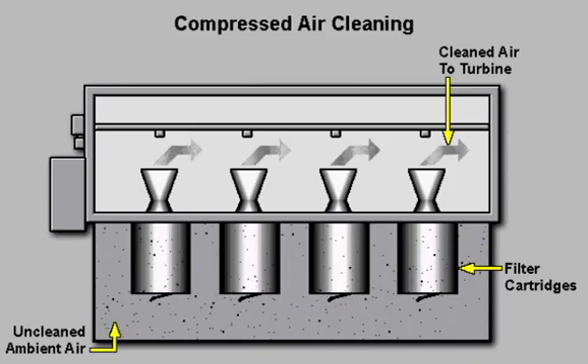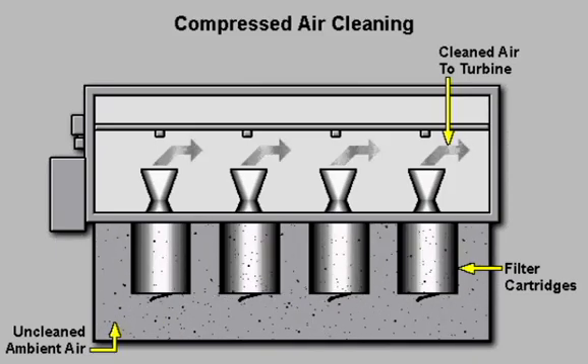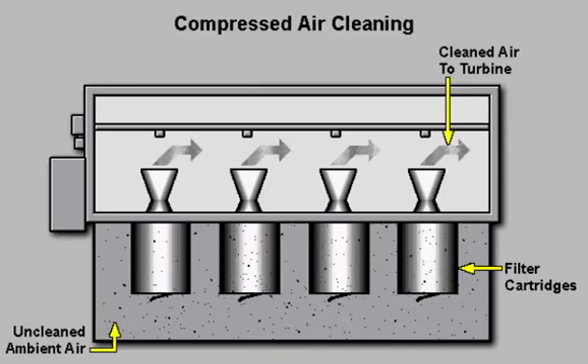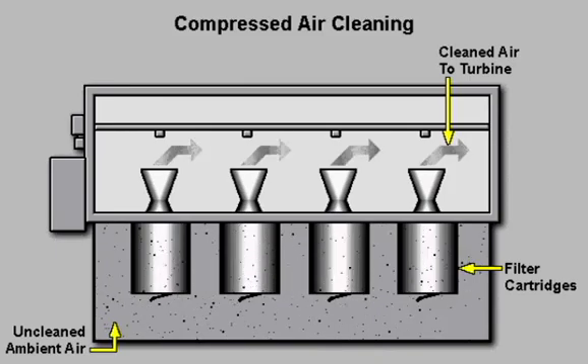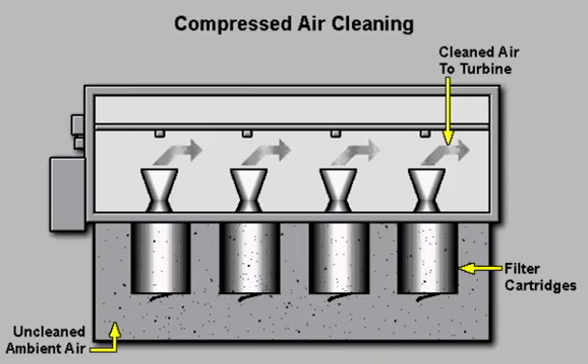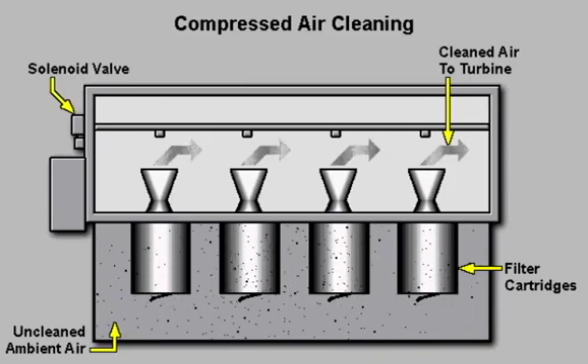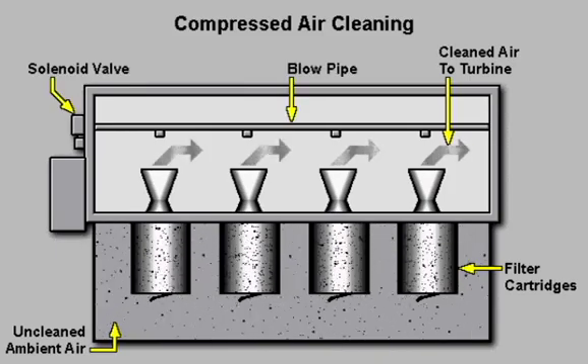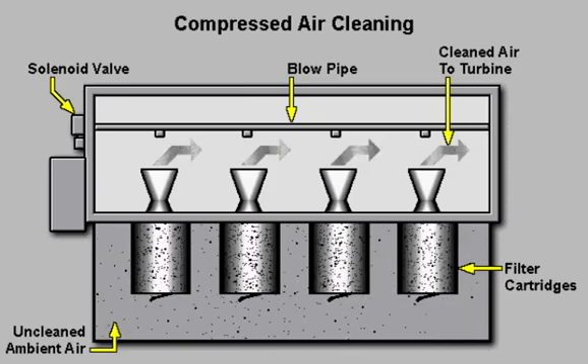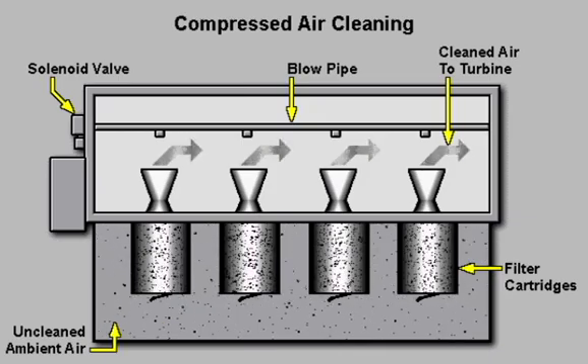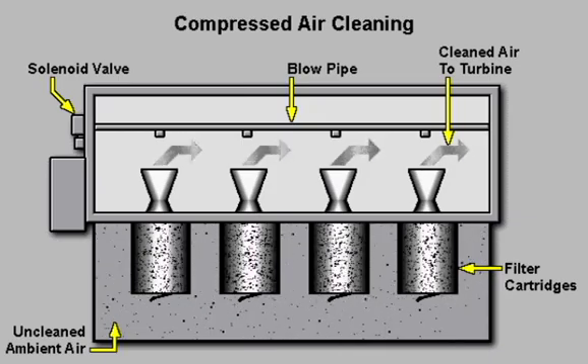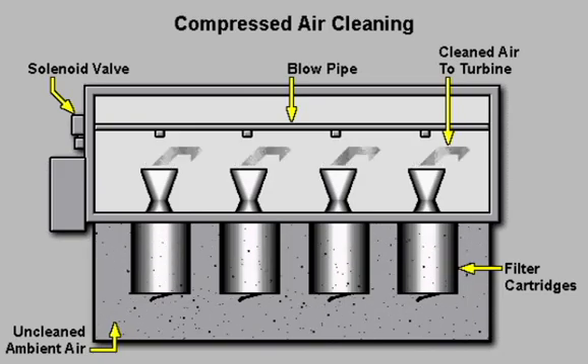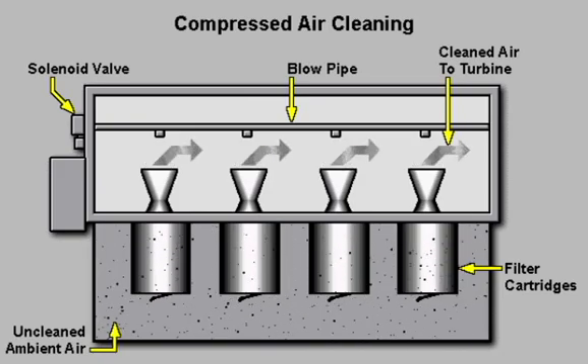When the control system senses that the self-cleaning filters are dirty, compressed air is delivered to the filters through a solenoid valve and blowpipe. A pulse of compressed air flows in a reverse direction through each filter and dislodges any dust adhering to the filter's surface.